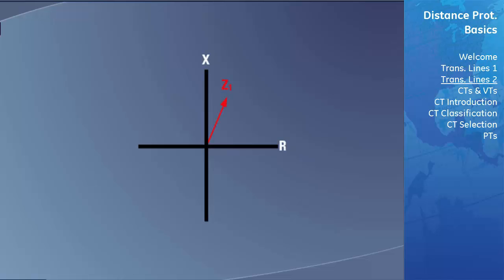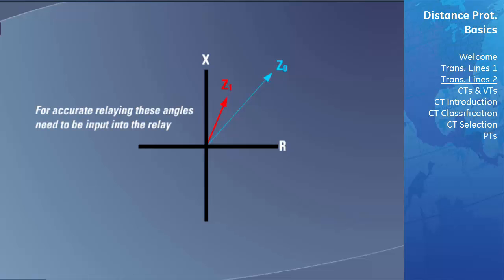Typical positive sequence line angles will be in the range of 70 to 85 degrees for lines 115 kilovolts and above. The corresponding zero sequence line angles are rarely the same as the positive sequence values due to the grounding of the line structure. For accurate relaying, these angles need to be input into the relay so it can properly model the positive and zero sequence impedances. This wasn't done for older generations of distance relays, and is why modern relays such as the D60 are much more accurate in detecting ground faults.